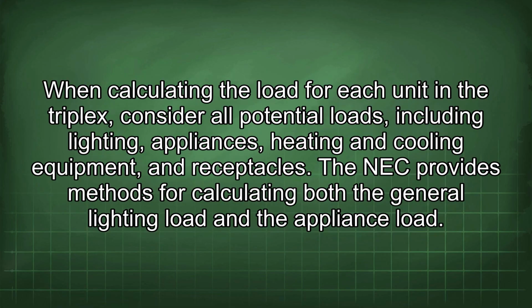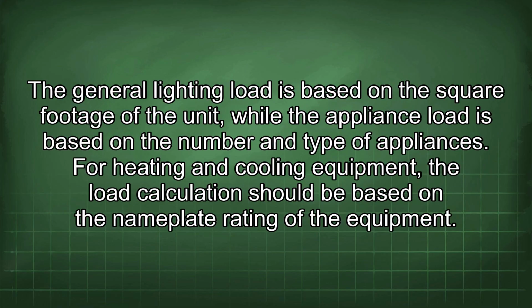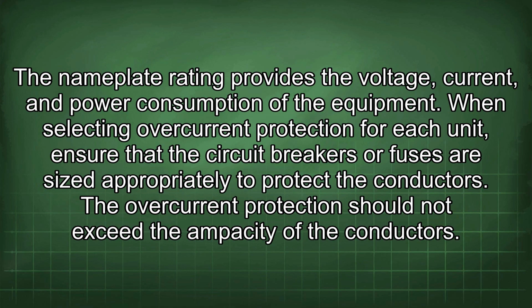When calculating the load for each unit in the triplex, consider all potential loads, including lighting, appliances, heating and cooling equipment, and receptacles. The NEC provides methods for calculating both the general lighting load and the appliance load. The general lighting load is based on the square footage of the unit, while the appliance load is based on the number and type of appliances. For heating and cooling equipment, the load calculation should be based on the nameplate rating of the equipment. The nameplate rating provides the voltage, current, and power consumption of the equipment.